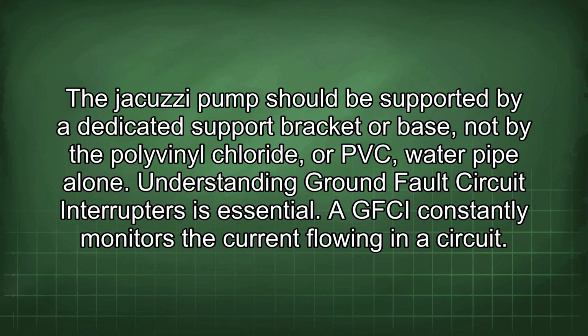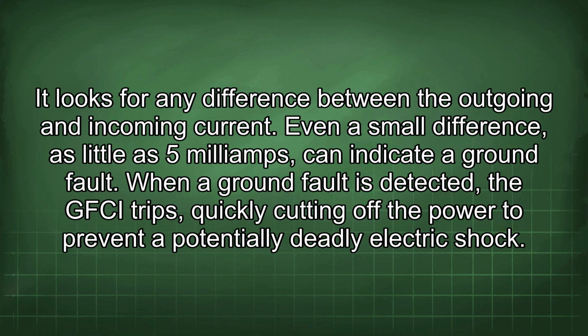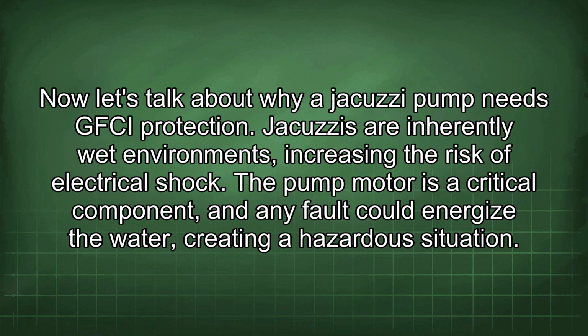A GFCI constantly monitors the current flowing in a circuit. It looks for any difference between the outgoing and incoming current. Even a small difference, as little as 5 mA, can indicate a ground fault. When a ground fault is detected, the GFCI trips, quickly cutting off the power to prevent a potentially deadly electric shock. Now let's talk about why a jacuzzi pump needs GFCI protection.